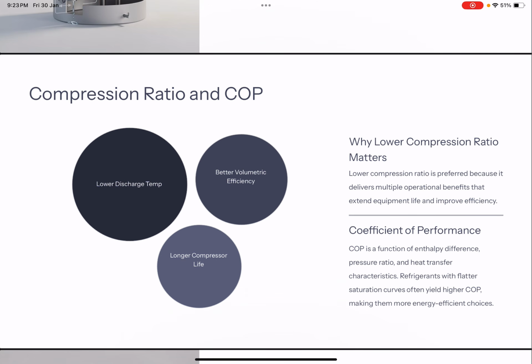If you want to use centrifugal compressors, then the vapor density has to be lower. The third important property is what is known as the compression ratio. A lower compression ratio is preferred because it would deliver multiple operational benefits that extend the equipment life and improve the efficiency. By compression ratio, we mean the delivery pressure upon the suction pressure ratio. It is also called the pressure ratio. And if the pressure ratio or the compression ratio is lower, then the discharge temperature is lower. If the discharge temperature is lower, the compressor life is more. Similarly, if the compression ratio or pressure ratio is lower, the volumetric efficiency improves.